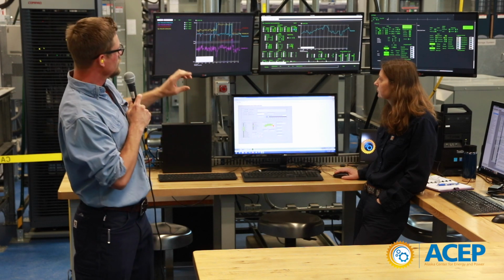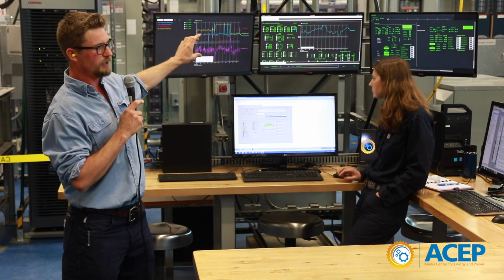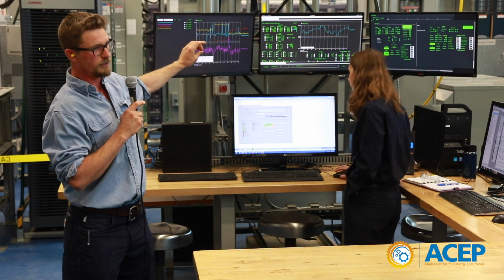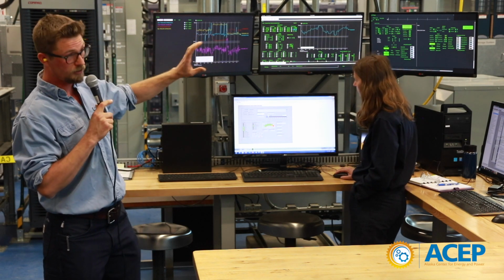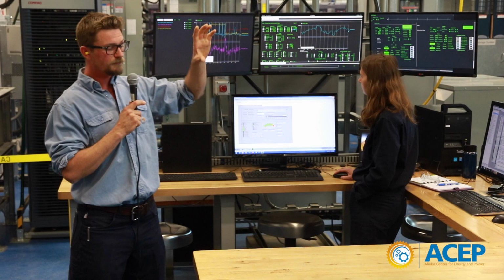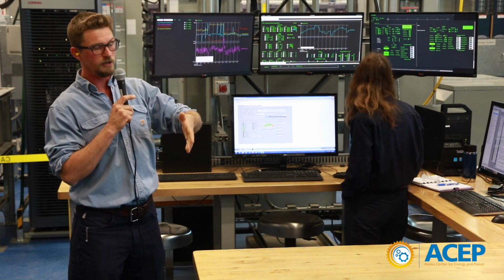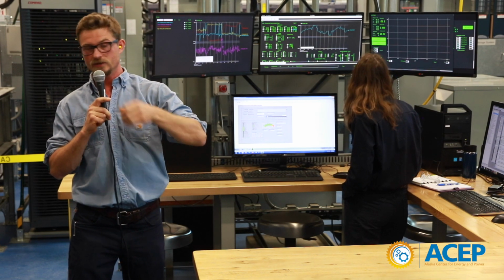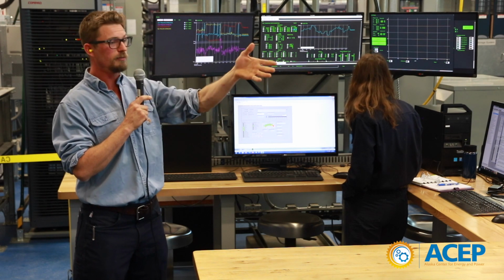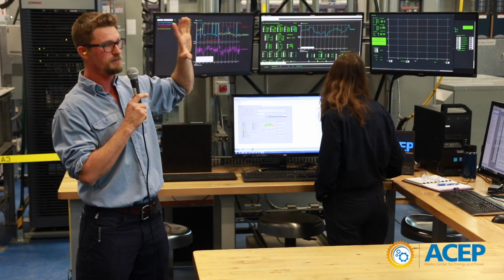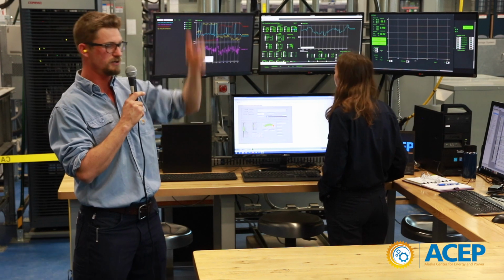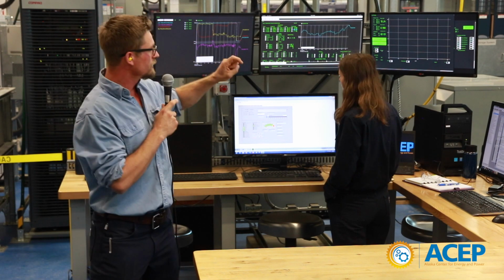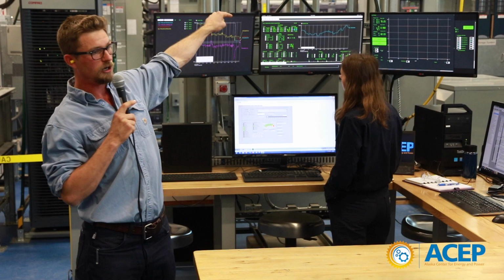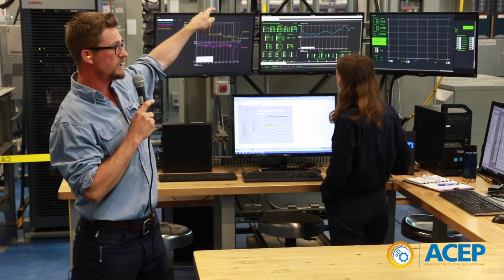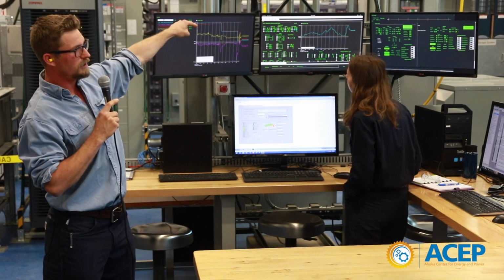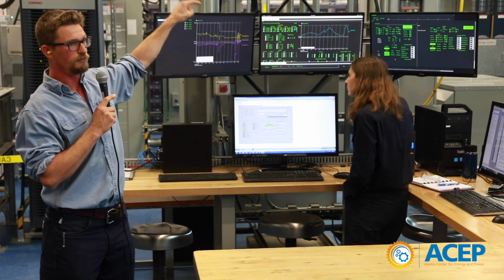The reason we couldn't put a smaller generator before, or turn the generator off, is because if there's a drop in the wind power, you need something there able to output that power. So you had to have a generator big enough to cover the whole load in case the wind power drops to zero. This inverter is what people call a grid forming inverter. Like Dave said, it's a very powerful inverter, and that inverter we have over there is able to form the grid.